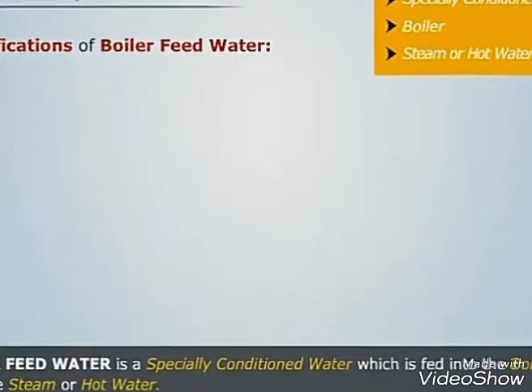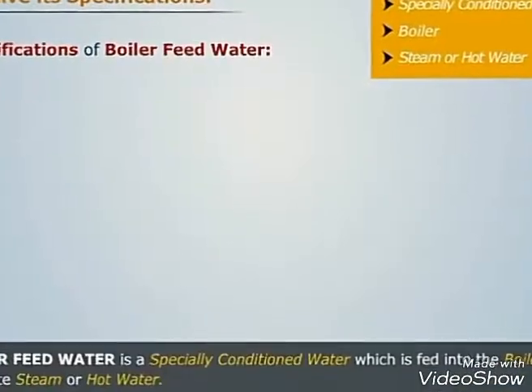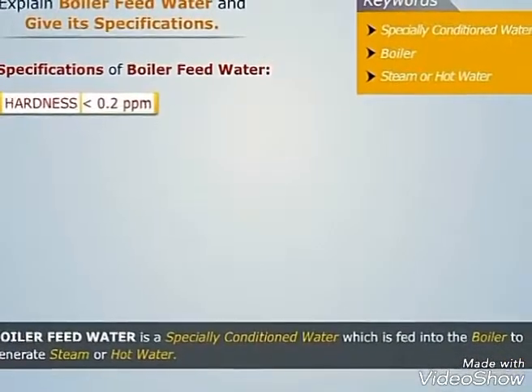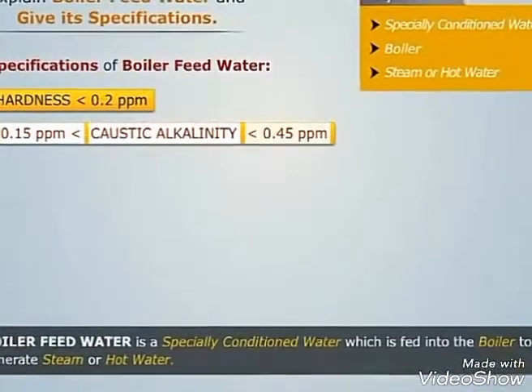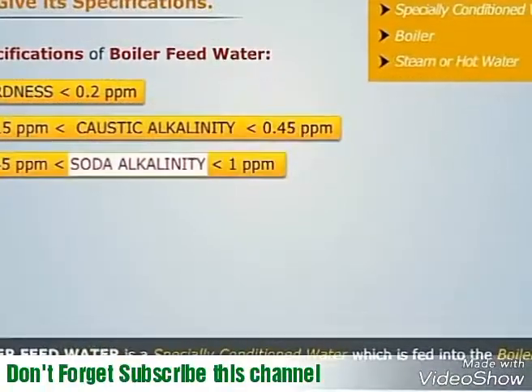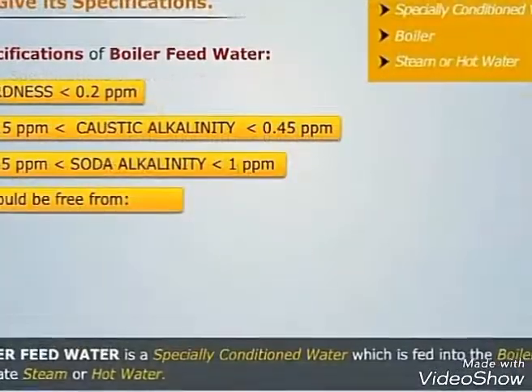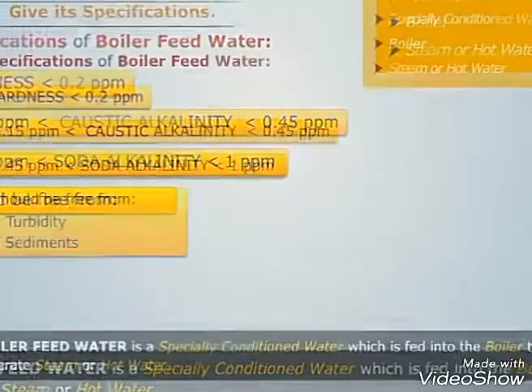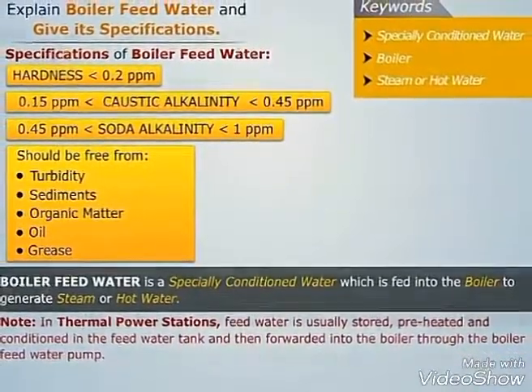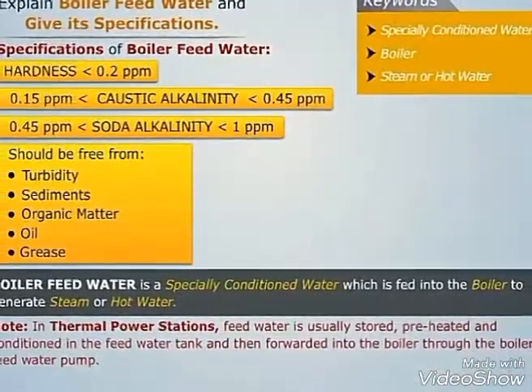Let us now discuss the specifications of boiler feed water. Before using the boiler feed water in the boiler, it should be made sure that it meets the following specifications: its hardness should be below 0.2 parts per million; its caustic alkalinity should be between 0.15 and 0.45 parts per million; its soda alkalinity should be between 0.45 and 1 parts per million; it should be free from turbidity and sediments; and it should be free from organic matter, oil and grease to avoid foaming. Note that in thermal power stations, feed water is usually stored, preheated and conditioned in the feed water tank and then forwarded into the boiler through the boiler feed water pump.